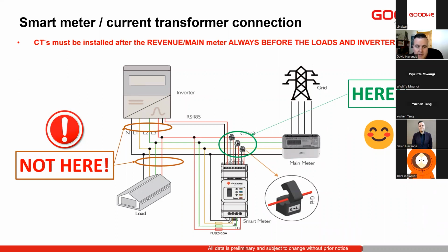So the CT cables here on top, you'll notice that A is on the right-hand side, but L1, which is A, is here on the left-hand side. It's very important to note this, that the bottom is from left to right, and the top is from right to left. You will find this in the user manual as well, so please always pay attention to that.